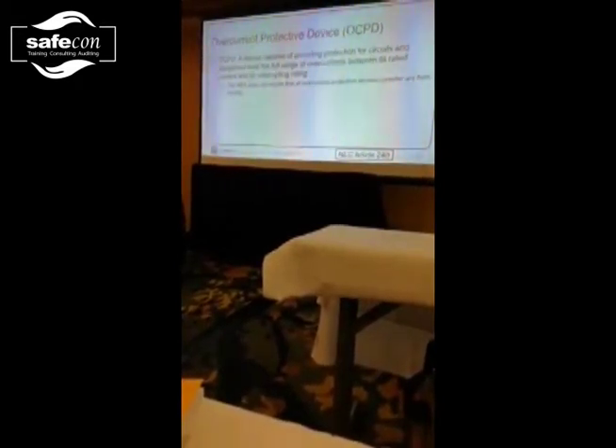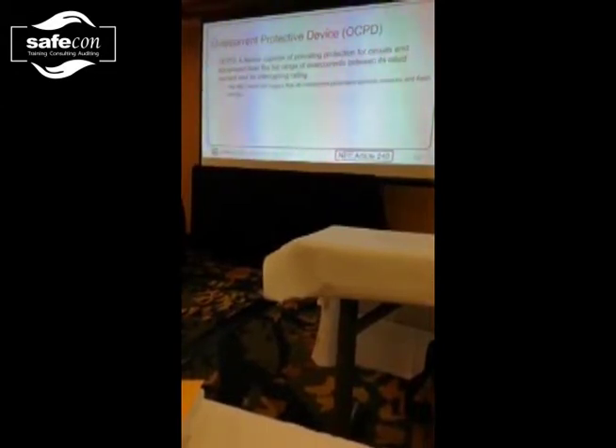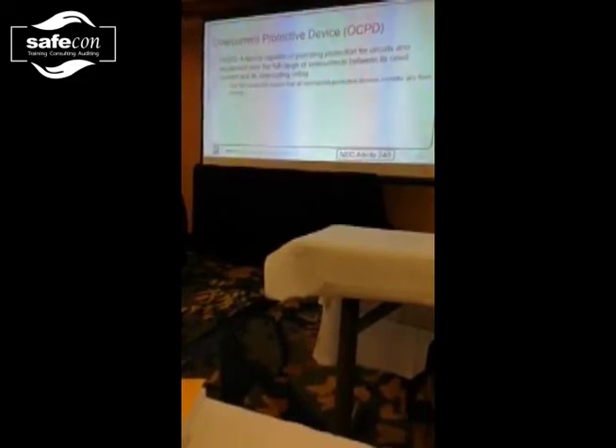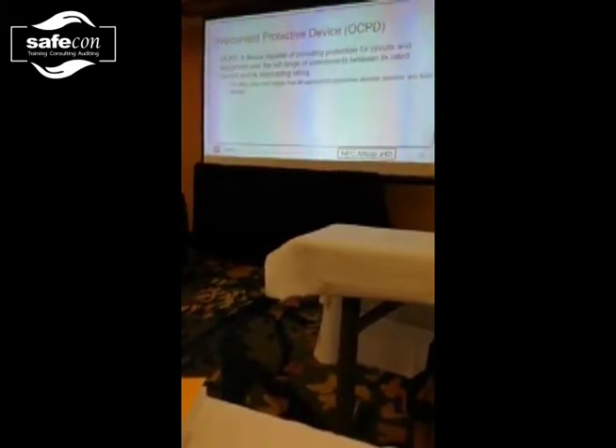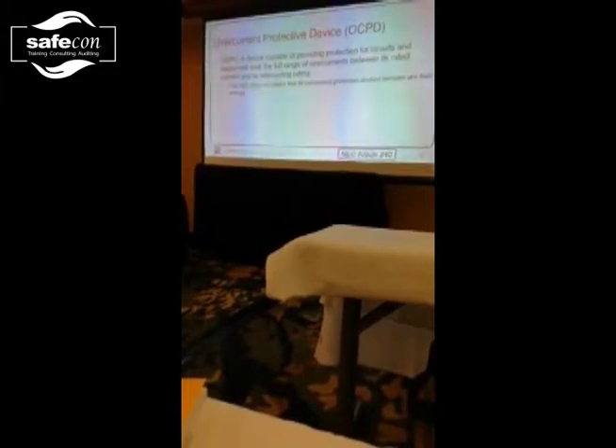We'll talk about them later on in Article 240. So the NEC is starting to consider arc flash, but it's at a pretty high level at this point. It's not going to be an 800 amp panel. It's going to be a 1200 or a 1500 or a 2000 amp panel board or switchboard or motor control center. You're going to have to employ some type of arc flash mitigation if it is a circuit breaker. In 2020, that will include fuse installations as well.